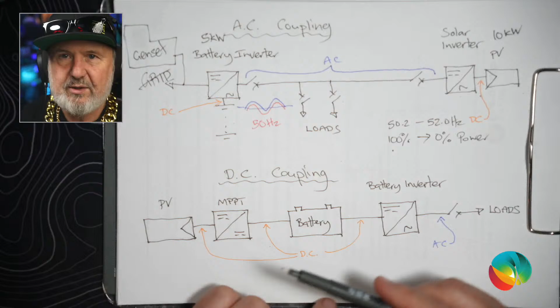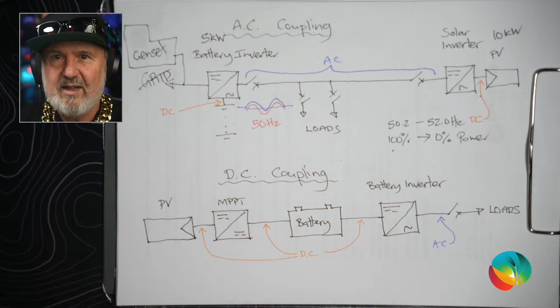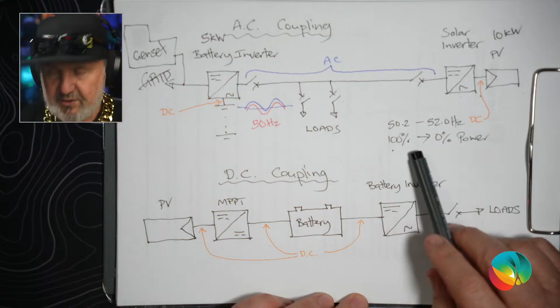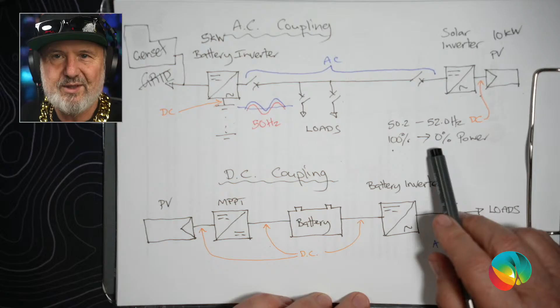If I'm trying to pump 10 kilowatts into a 5 kilowatt inverter, I better control it real fast because I could damage it. In reverse, it's still got the same limitations as when it's generating forward. So how do we stop that happening? Now, frequency shift, which is what this is called, frequency shift power control, can only work as fast as a 50 hertz signal, which is around 20 milliseconds from peak to peak.